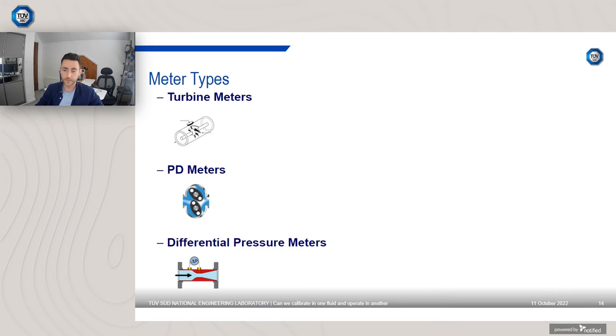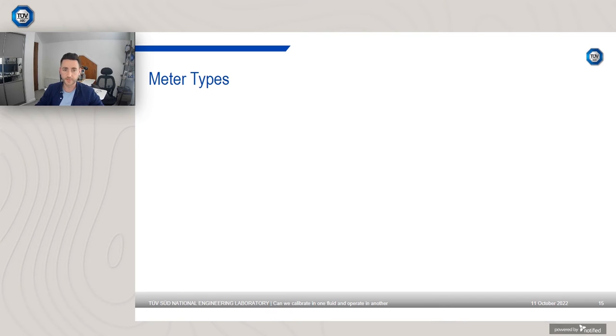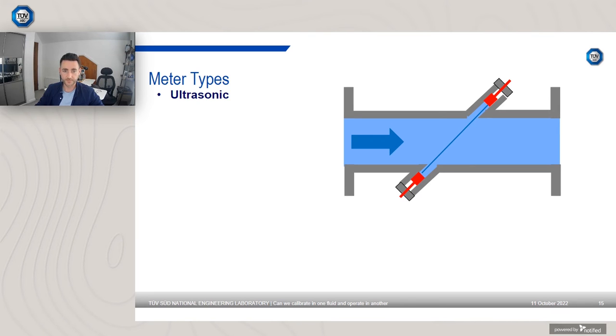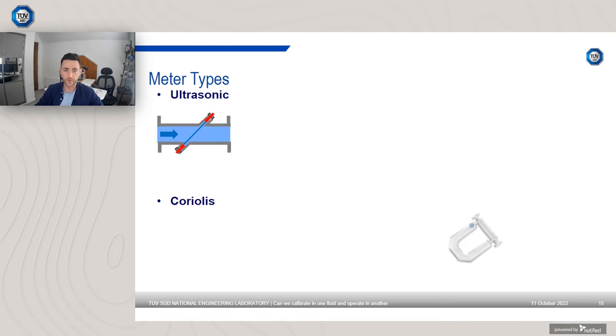Now, what about the newer, let's say these are more historical type flow meters, and then we're looking at some of the newer technologies. One of the more common ones is the ultrasonic meter. Now again, you get gas ultrasonic meters and you get liquid ultrasonic meters, but they are designed purely for that fluid. So a liquid ultrasonic shouldn't be used with gas, and the same is true for a gas ultrasonic, it shouldn't be used with liquid. Due to the design, different transducers operating at different frequencies, they're not suitable. So you couldn't calibrate an ultrasonic meter in water and then successfully use it with natural gas, which is a common question we get asked, but it's not possible.